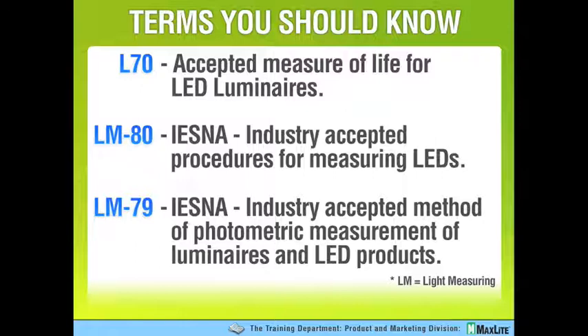This is a very different way of measuring the lifetime of a light bulb or fixture. Previously, we have always measured life by a 50% failure rate. When you look at a 1,000-hour incandescent or a 10,000-hour CFL, that lifetime was determined by a 50% failure rate. For LED, because a quality LED doesn't actually fail but just continues to depreciate over extremely long periods — which can make it unsafe in exit signs and streetlights where you can't have them fading to barely visible — they use a standard called L70.